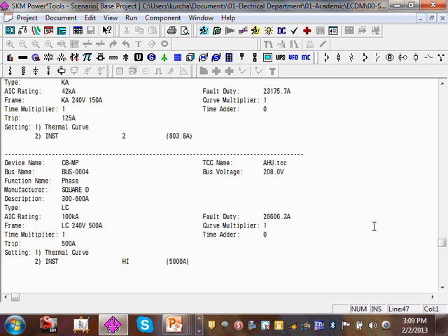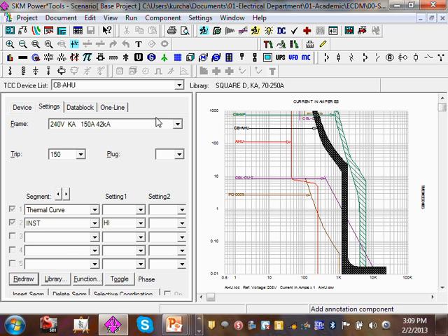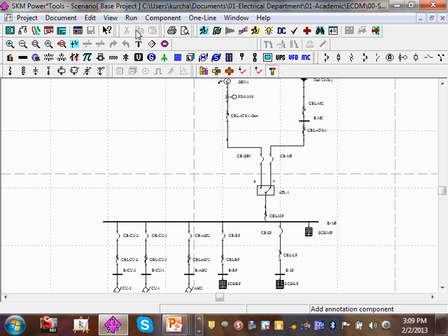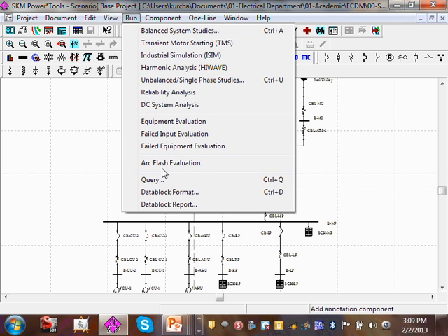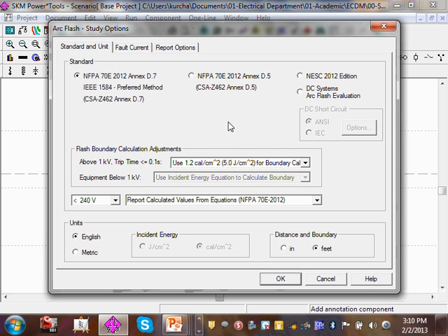Okay, so that's basically the overcurrent protection device. Let me show you how this impacts your arc flash, right? Let's go to the arc flash. So directly into my arc flash analysis. Here's my arc flash analysis, just to give you an idea. When you go to the arc flash, the software allows you to use IEEE 1584. That's the most common one.